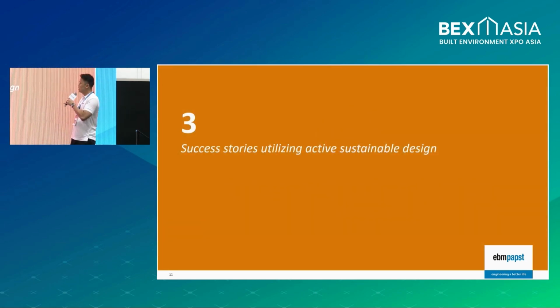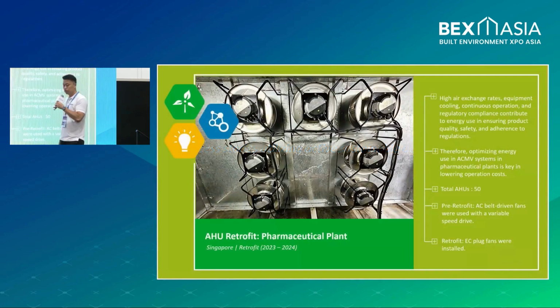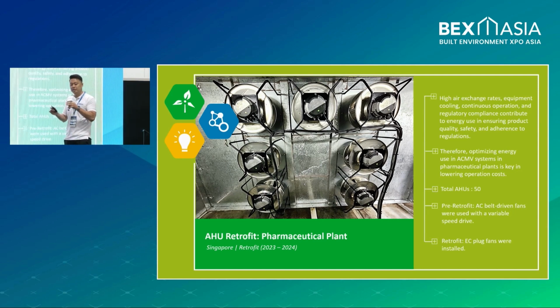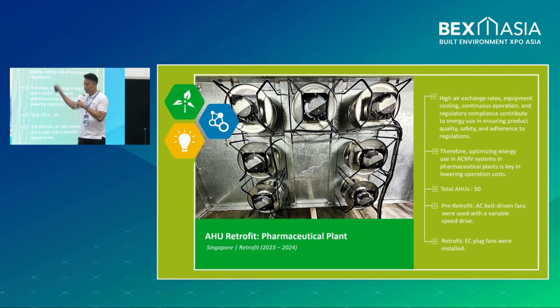Success story utilizing active sustainable design. So we talked about one of the case studies in one of the pharmaceutical plants in Tuas area. From this picture, we are converting an AC belt-driven system with VFD to an EC fan grid system. It needs about 7 EC fans because of the high airflow, more than 50,000 CMH.